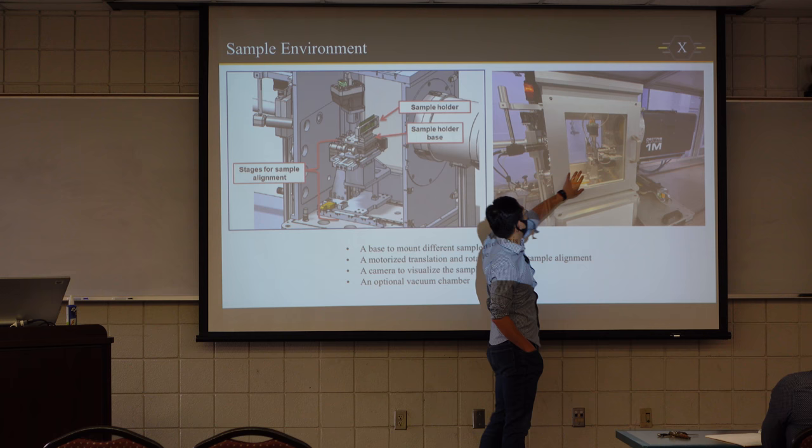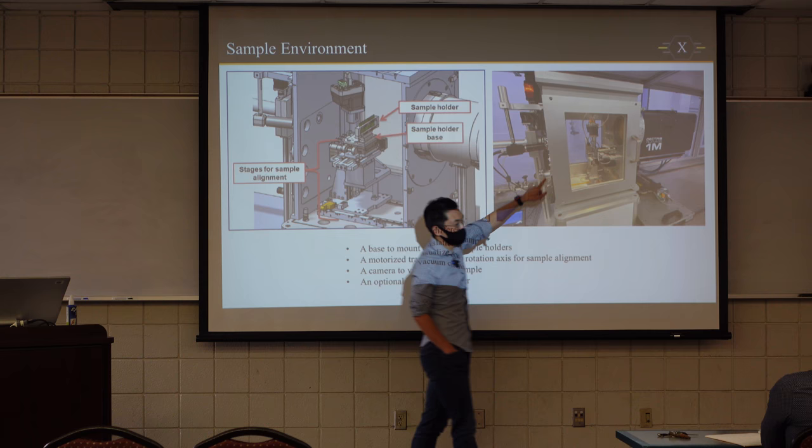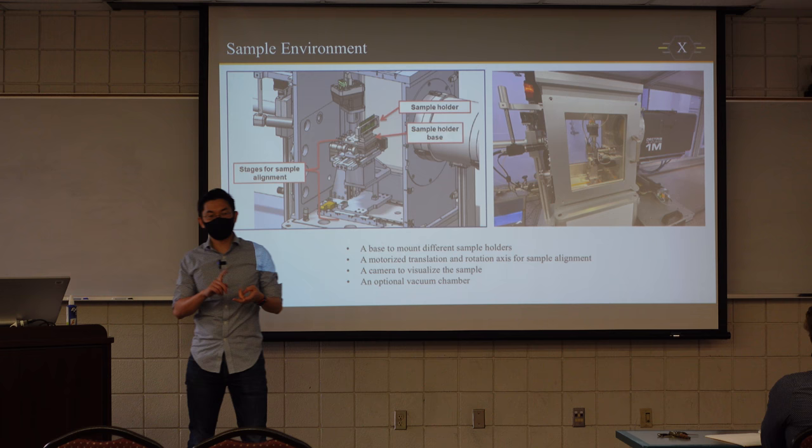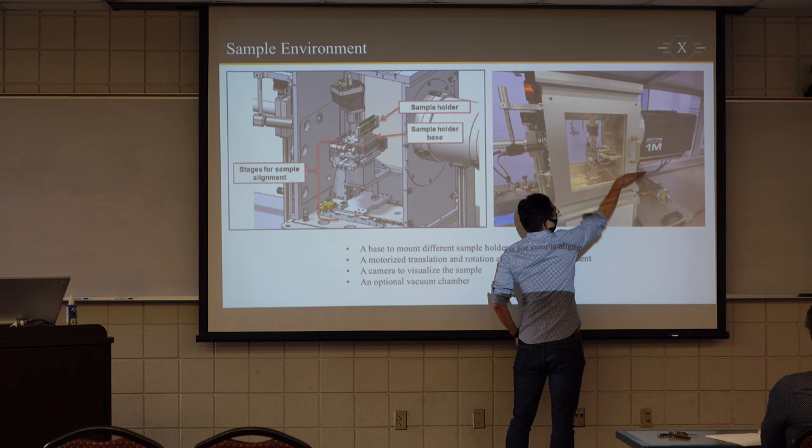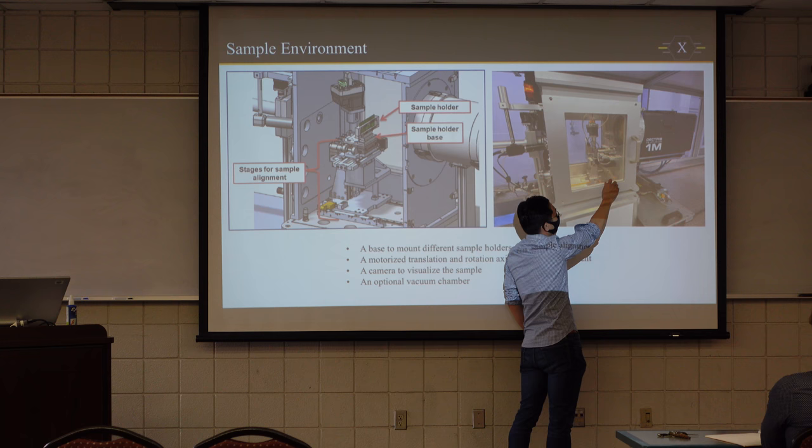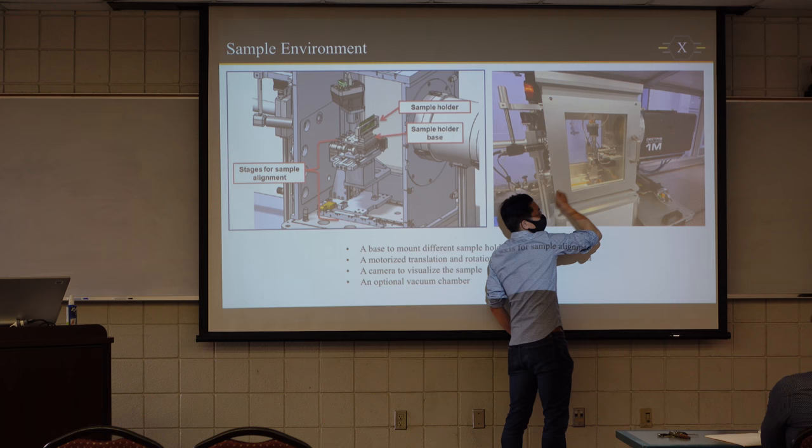So this is a stage assembly. It's actually relatively complex. It has a linear stage in the X and Z directions. It doesn't have a stage in the Y direction, so moving in and out, you're going to change the sample to detector distance. That stage is manual, which means you can manually lift up. There's a mount. You can lift up and shuffle this whole stage assembly on a rail.